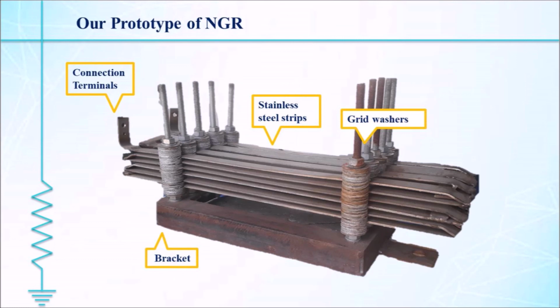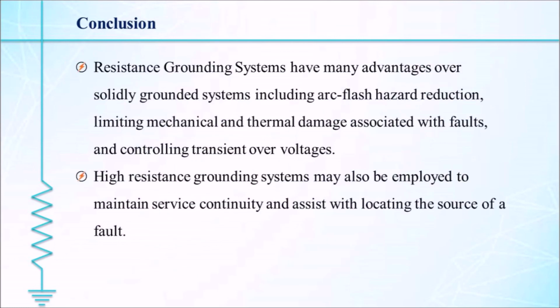Actual NGR is formed by stacking a number of stainless steel strip resistive banks together as per the requirement of the customer. So, the conclusion of the topic is that the NGR system provides more benefits than both the ungrounded and solidly grounded system. NGR gives protection against transient overvoltage. The main ultimate aim of the NGR is to limit the fault current. It just works as a fault current regulator. The resistance always opposes the flow of current.